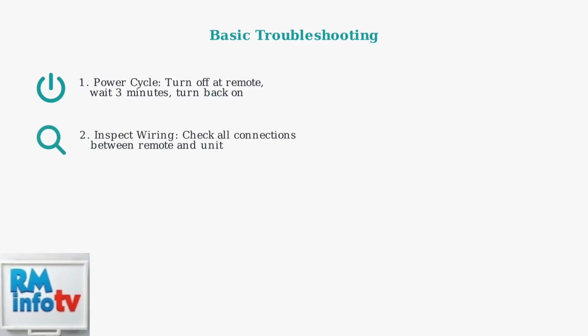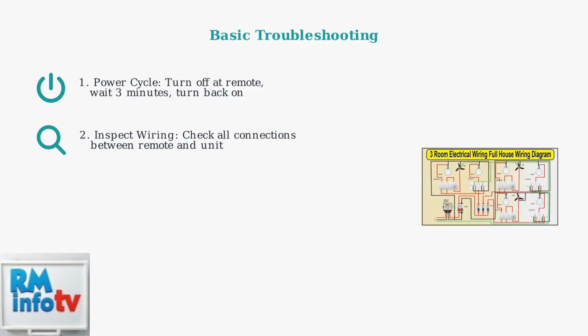To begin troubleshooting, first power cycle the unit by turning it off at the remote control, waiting a few minutes, and then turning it back on. Next, carefully inspect all wiring connections between the remote and the unit, ensuring they are secure and free from damage. Proper wiring connections are essential for communication between components. Look for loose connections, damaged insulation, or corroded terminals.